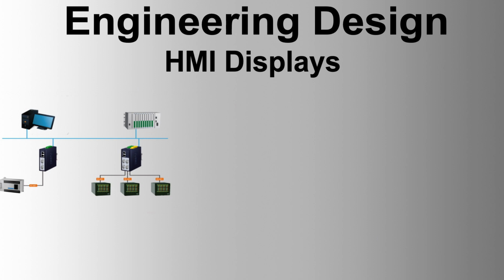Function keys. Function keys are one-touch operation keys that can be configured to call up displays, windows, faceplates, and initiate sequences or application programs. They minimize the typing of frequently used commands and requests, reducing the time required to access a display or initiate a sequence. They also reduce the memory load of the operator and the risk of typing errors. Function keys should be arranged logically and consistently to clearly indicate their purpose. Secondary confirmation should be required for initiating sequences or application programs to prevent inadvertent entries. Function keys are equipped with LEDs that can be configured to aid the operator in responding to alarm conditions.